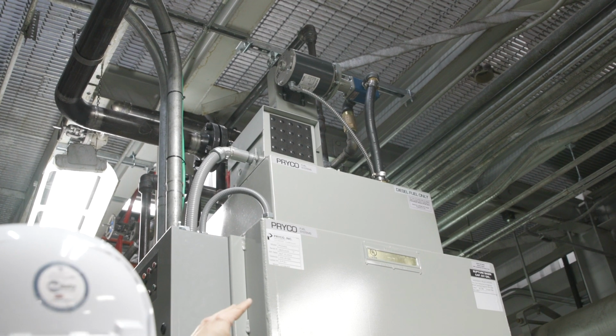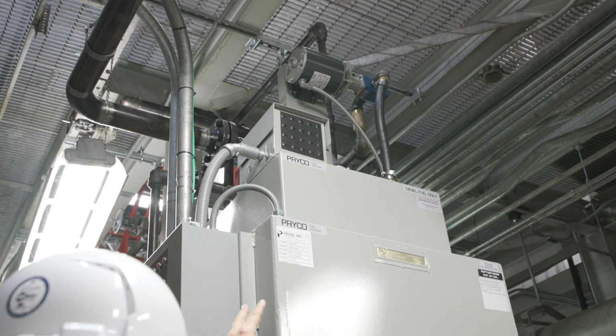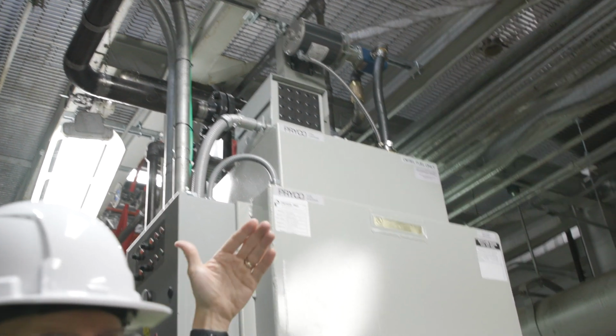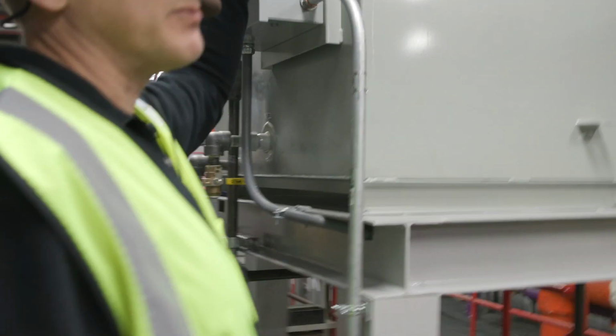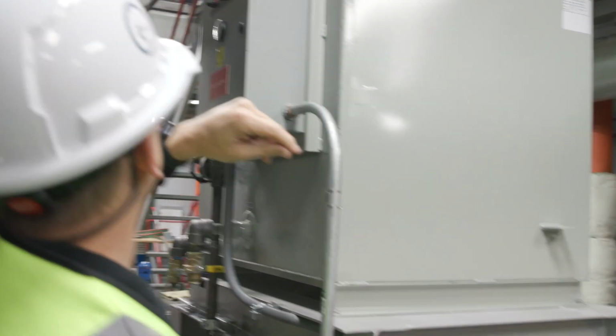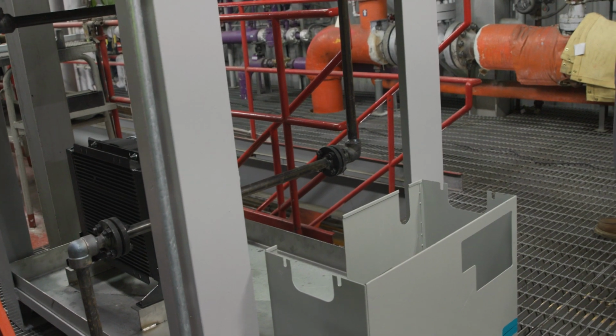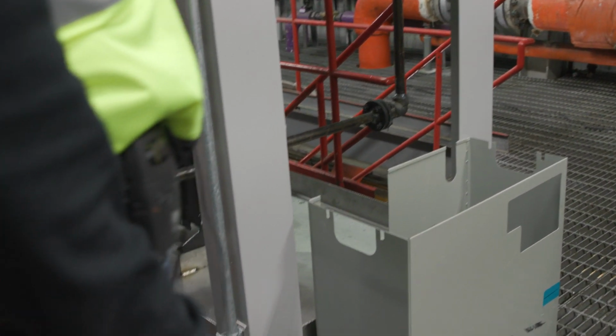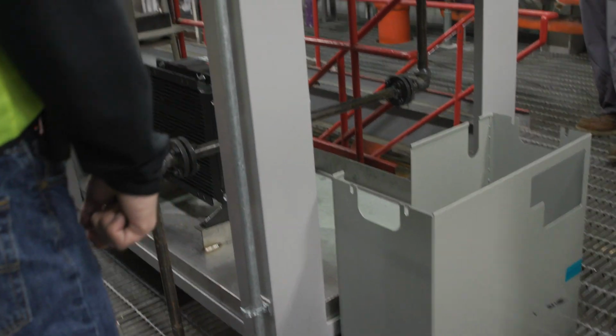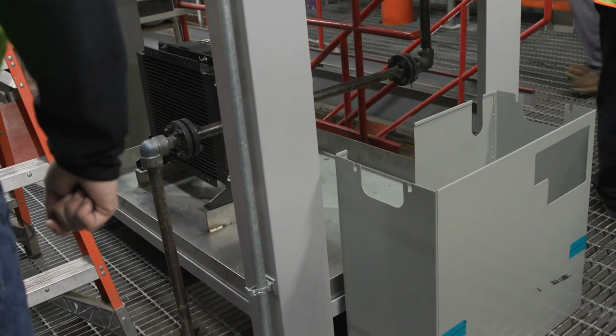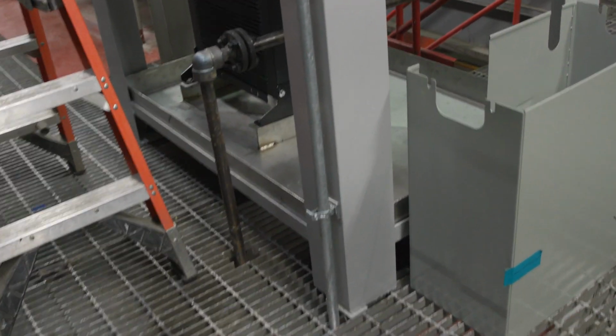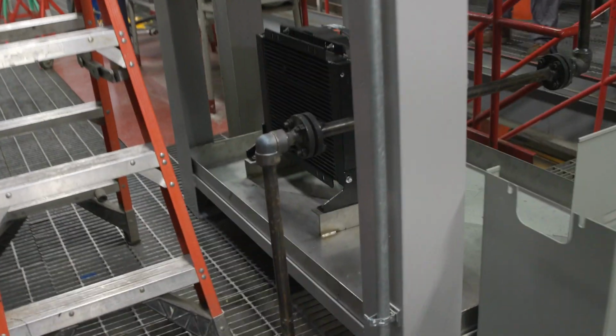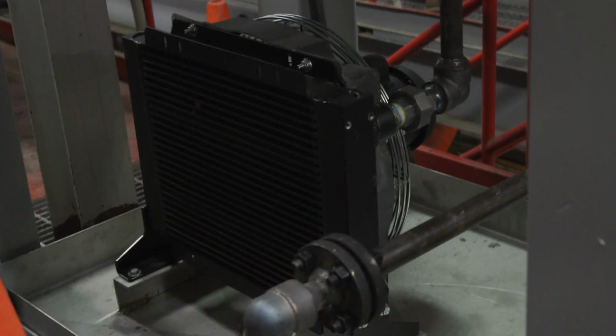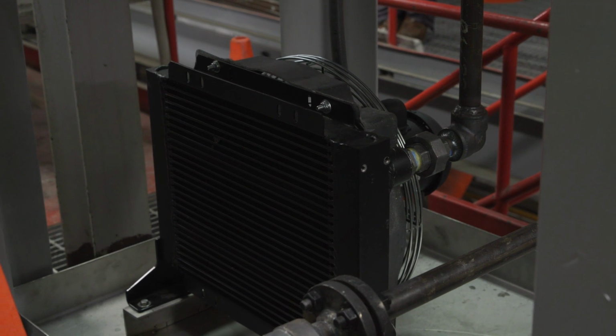There's also 2 sets of emergency shut-off valves as well. So if we get a high level indication, then we'll shut those valves as well. And then you just got your piping to and from the bulk tank along with their isolation valves as well. Again, fuel cooler on bottom. Fuel cooler fan will come on when we get a diesel run command from our PLC into this fuel control panel.